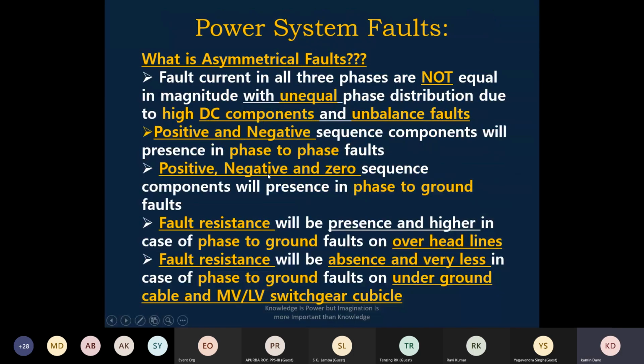Okay, what is asymmetrical current? Asymmetrical current means the magnitudes of the three phases are not equal, and the phase angles of the three phases are also not equally apart. So that is called asymmetrical faults. This is happening due to the DC component and unbalanced fault conditions. High DC component.